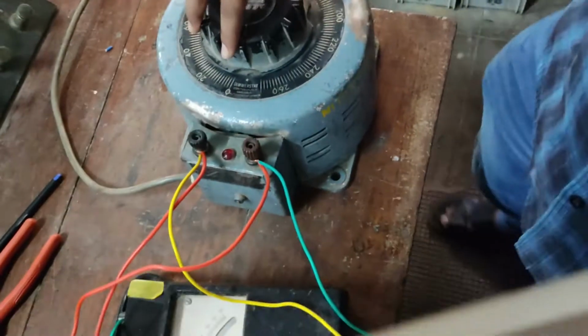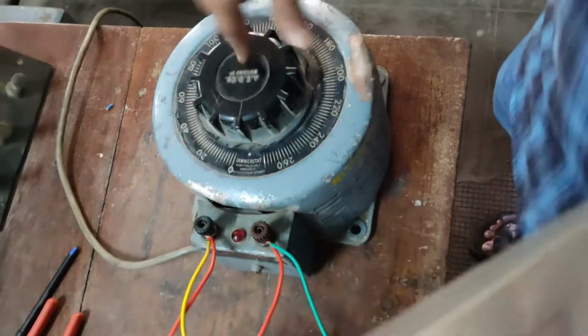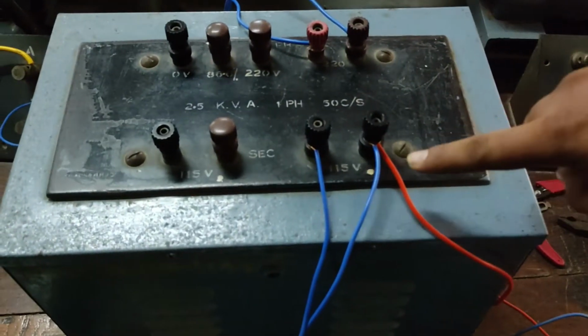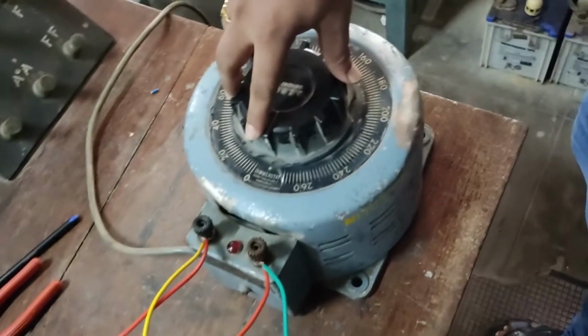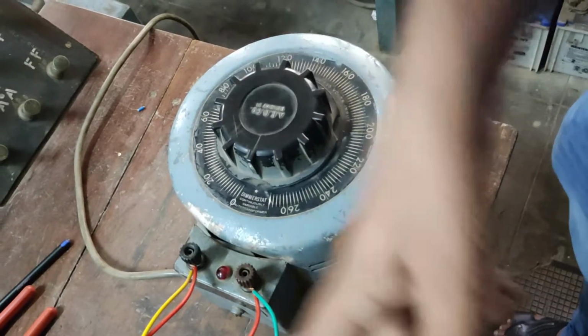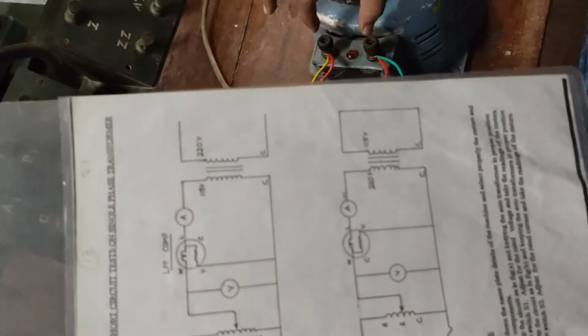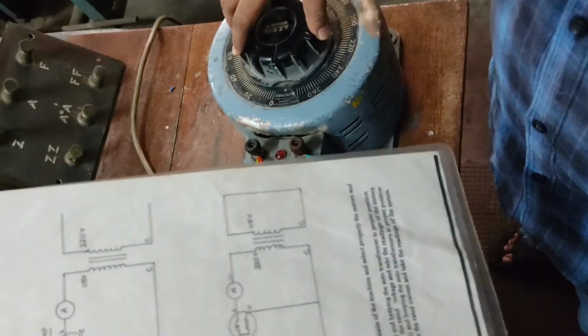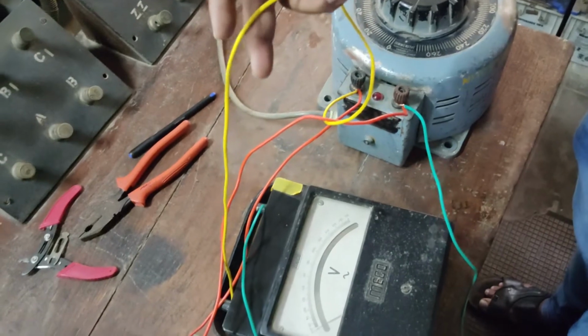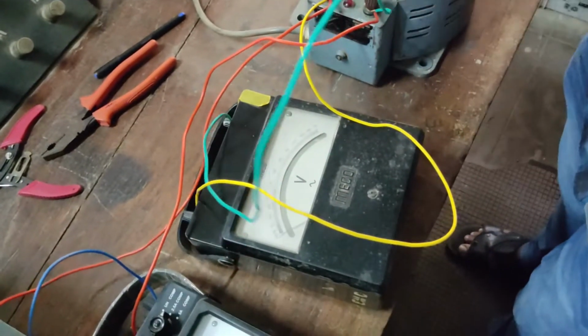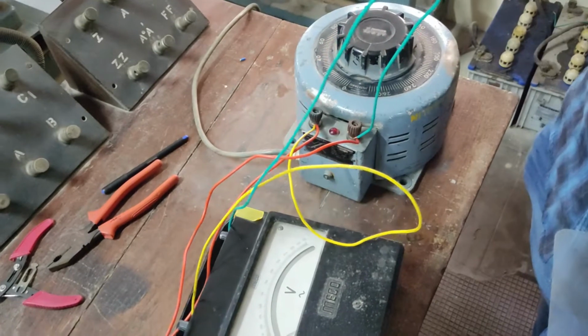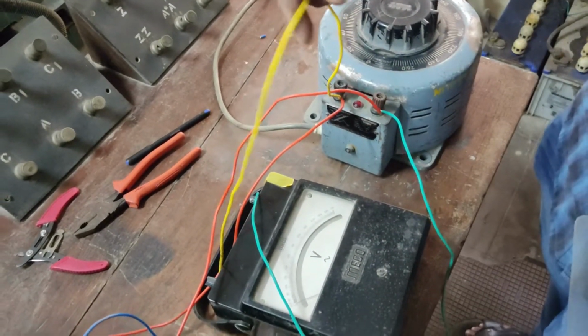From here the supply we can vary from 0 to 260 volts, but as per our transformer rating, for the OC test 115 volts is enough. So based on this, we can vary only up to 115 volts, and that voltage we can see here. According to this circuit, the voltmeter has to be connected across the supply of the auto transformer. This is AC, so we can connect either of the terminals, phase or neutral. But as per understanding, we have taken this as the phase and this as the neutral, and two terminals are connected across the supply.